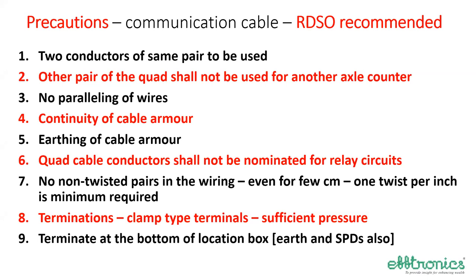Quad cable conductors shall not be nominated for relay circuits. Because we have a six quad cable and we are only using four conductors and the other five quads are spare. So can we connect a relay? No, it is not permitted. Because when a relay drops, it gives an electrical kick or surge of up to 500 volts. It may last for only microseconds, but that is sufficient to damage any electronic equipment. In fact, shelf type relays used to give 1500 volts. Q style are a little less comparatively. So relay circuits shall not be used in this quad cable.